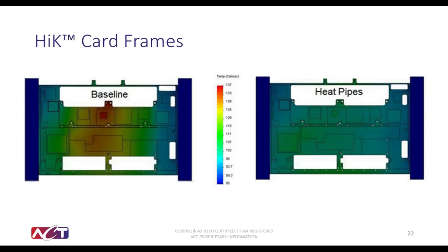This next slide shows an example of these high-K card frames. Again, by embedding heat pipes into that aluminum conduction card, ACT is able to reduce the maximum temperature seen by those components by 20 to 30 degrees C by adding no moving elements and no additional energy cost.